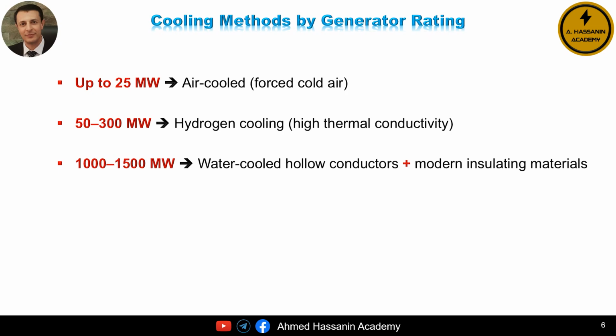and temperatures under control. When we reach very large generators, in the range of 1000 to 1500 megawatts, even hydrogen cooling reaches its limits. In these machines, the stator conductors themselves are designed as hollow copper conductors, and cooling water flows directly through them. This direct water cooling combined with advanced insulating and structural materials allows these massive generators to operate safely and efficiently under extreme power levels.